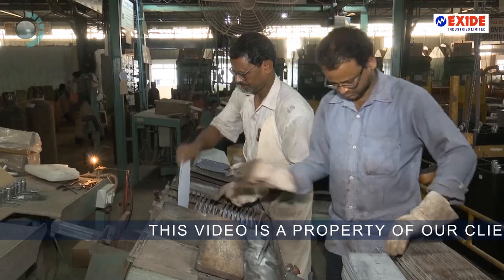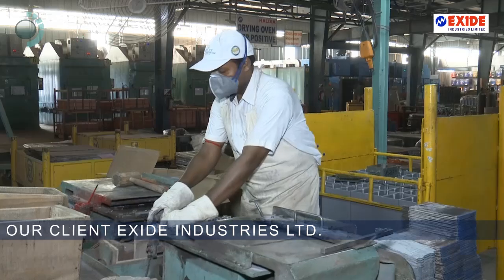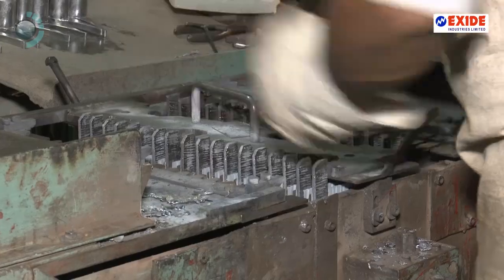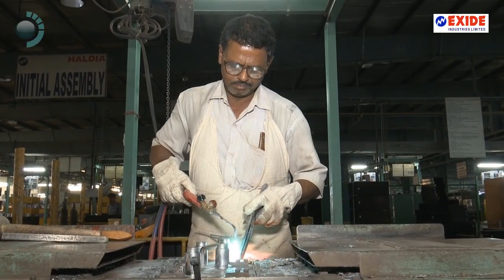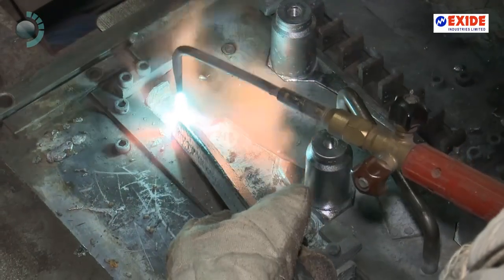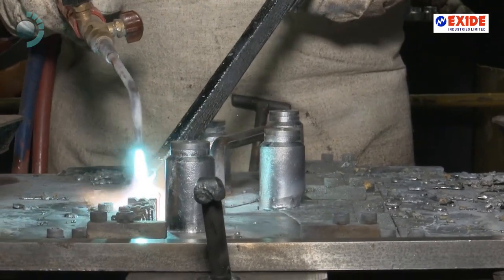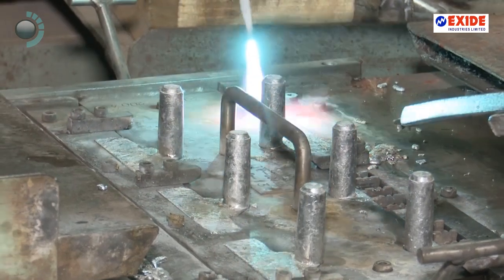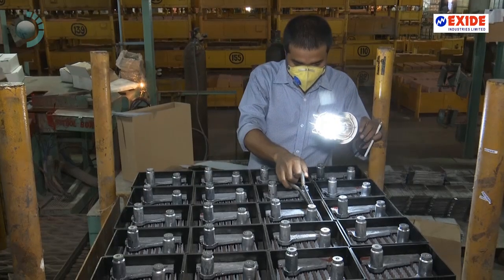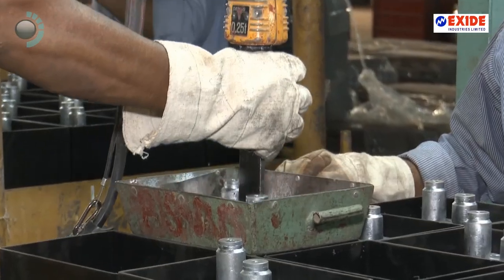The assembly of the thin end negative plates, positive plates with separators, and the thick intermediate negative plates are stacked within a comb structure in an alternate fashion. Gas welding is carried out using lead antimony burning sticks for the lugs to melt and weld together. Superior bolt-on terminals with specially grooved neoprene grommets arrest electrolyte seepage, preventing terminal corrosion. Temperature and density checks are carried out before the entire set is placed inside the container with lids.